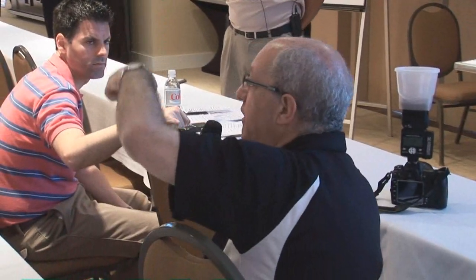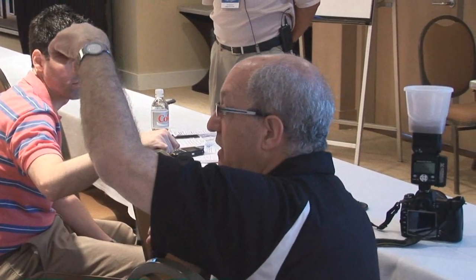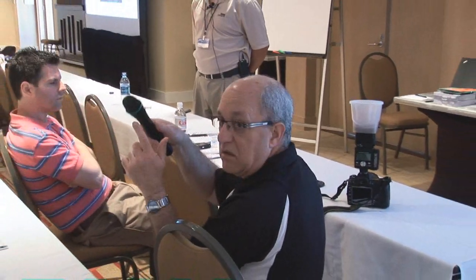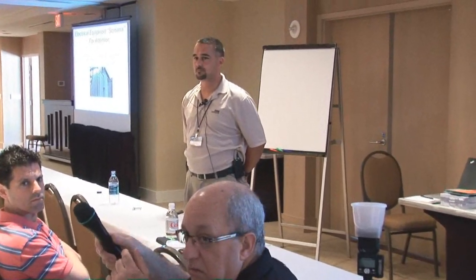I just want to add, on insulators, the center metallic post - over time, because of oxides turning into nitric acid with moisture, it will eat away at the center metal post and the insulator could break loose over time. You also get hairline cracks in the insulators themselves. Yes, and hairline cracks can occur.